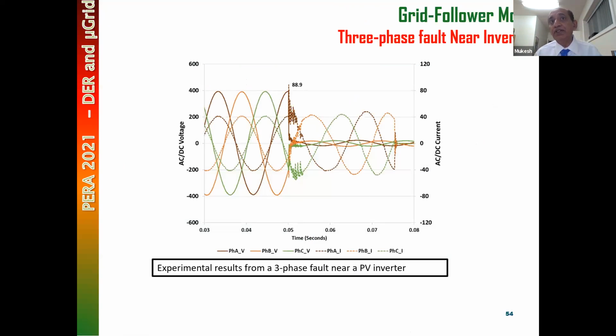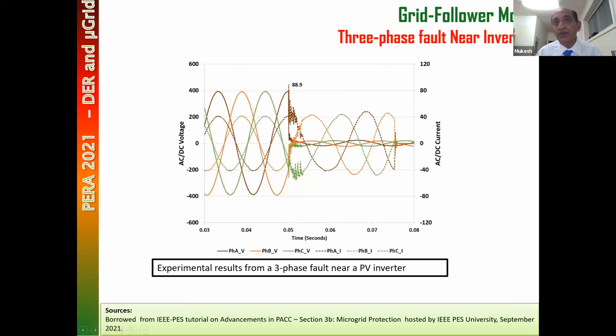Just to give you an example, this slide is borrowed from a tutorial. It is showing an inverter source. This side of the y-axis shows the voltages, this side shows the current. A three-phase fault is applied. Look, the voltages are nicely balanced. These are the currents before the fault, and then a three-phase fault is applied. Initially there is some transient and the three-phase voltage collapses. And the three-phase current is almost equal to the pre-fault current.